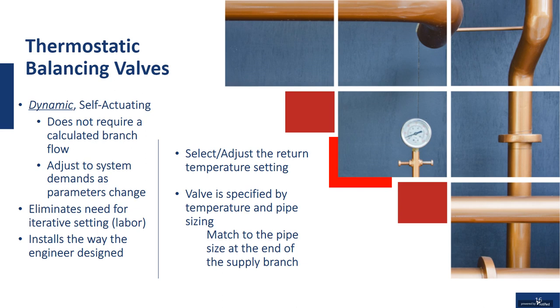You don't have to worry about something changing the system. Maybe they expanded the building, or maybe they shut off floors of a building or whatever, where the balancing would have to change. You don't have to worry about that with thermostatic balancing valves. So again, that installs the way that you as the engineer or designer design the system.